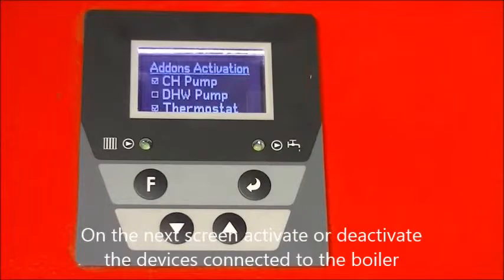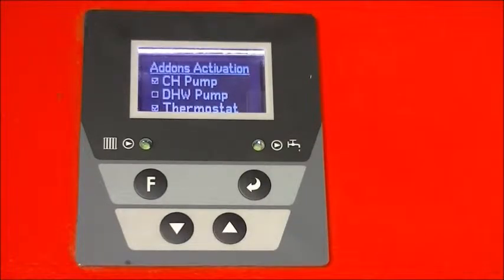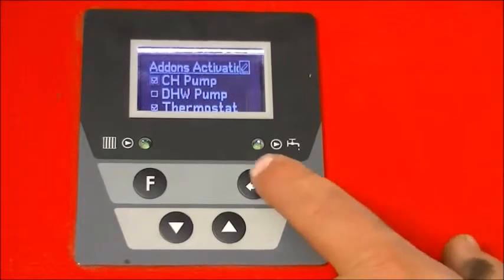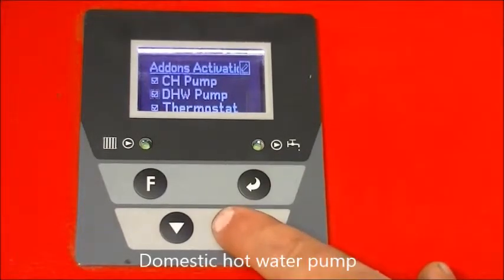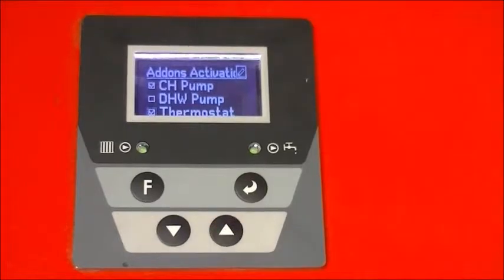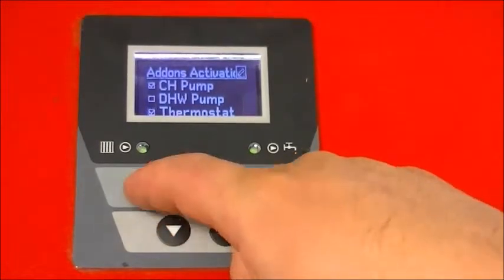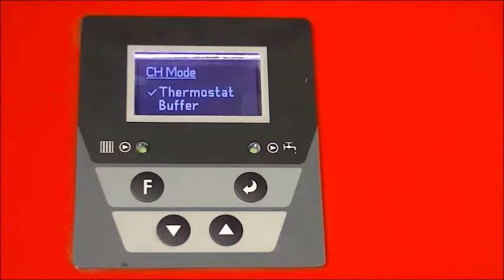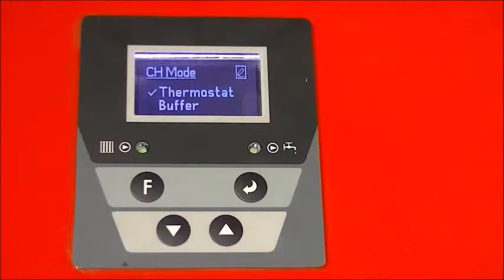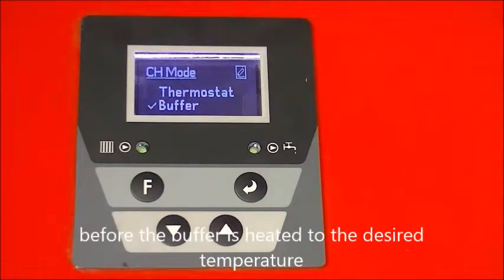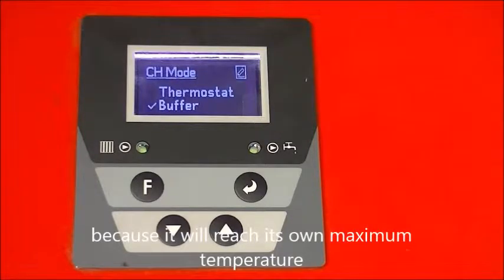On the next screen activate or deactivate the devices connected to the boiler: the central heating pump, domestic hot water pump, and room thermostat. On the next screen choose how to control the boiler — it can be by the boiler thermostat temperature or the buffer temperature. If the second option is chosen, the boiler may still stop before the buffer is heated to the desired temperature because it will reach its own maximum temperature.